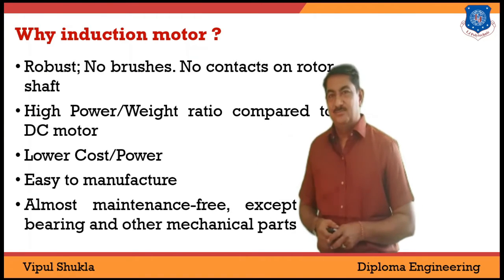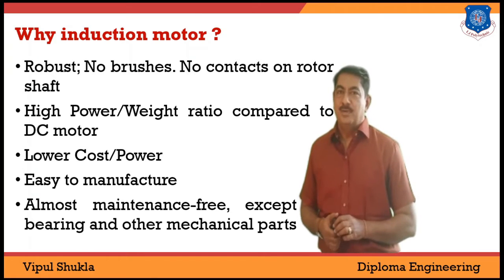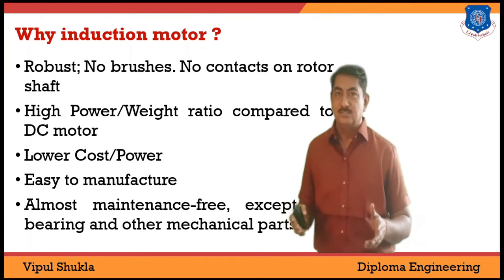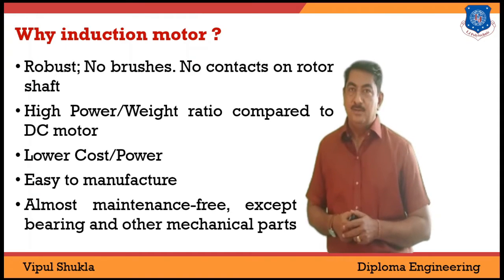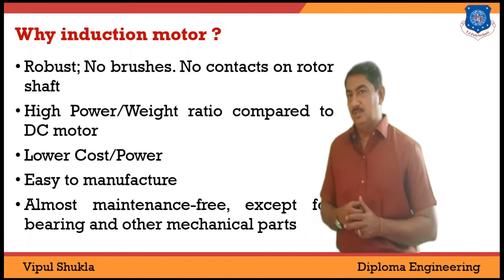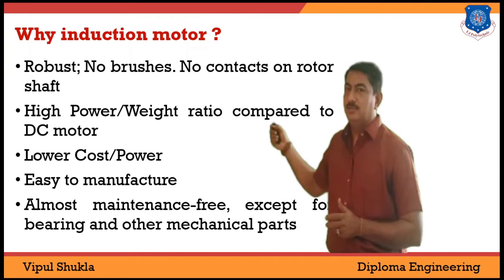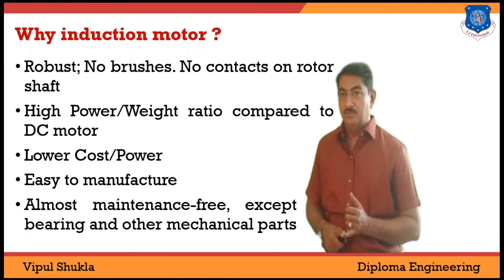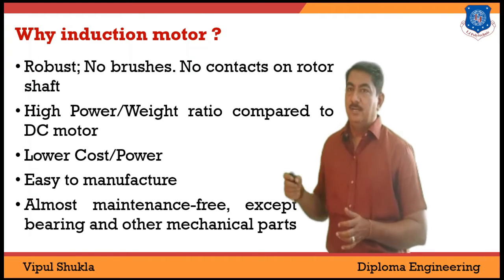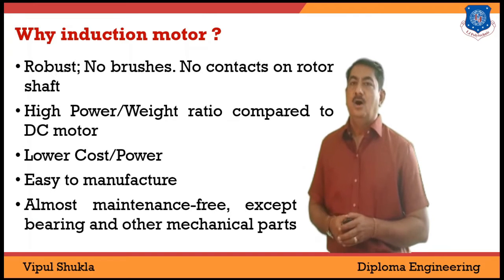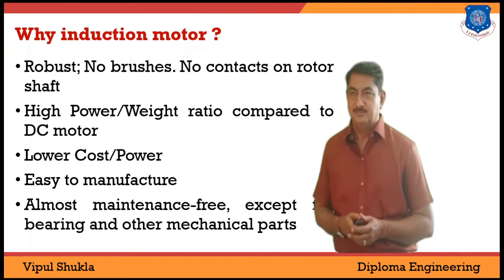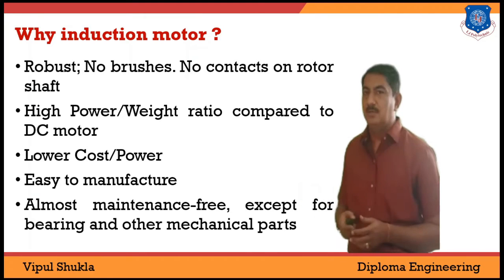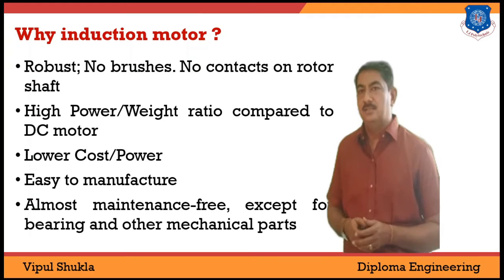Why use an induction motor? The reason is that it is robust, has no brushes, and no contacts on the rotor shaft — that is the main advantage. Also, it has a high power-to-weight ratio compared to the DC motor. Cost is also very less, power consumption is also less, and the manufacturing process is very easy. It is almost maintenance free, except for the bearings and some other mechanical parts which require a little bit of maintenance.